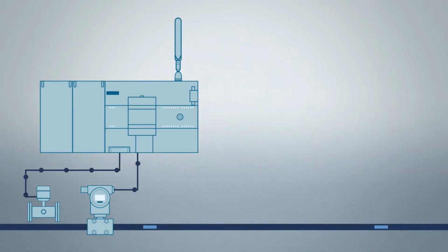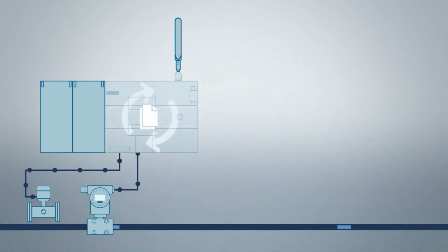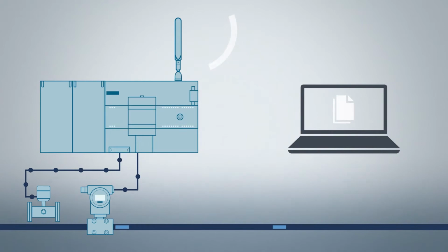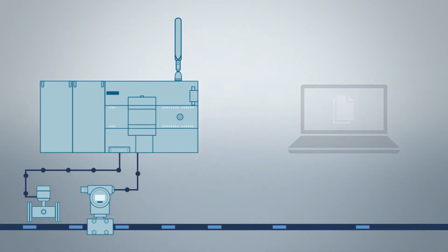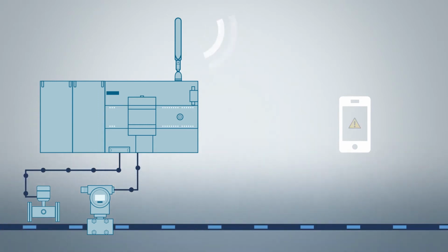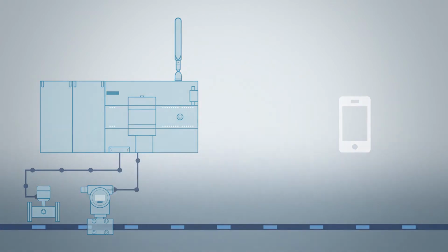The RTU monitors the pressure progression at the sensor. Via the counter input, it determines the flow rate and cyclically writes it to a CSV log file. The file is then sent by email once a day. As soon as the pressure rises above a certain limit value, the RTU sends an alert text message. In doing so, the current pressure value can be included in the text message.